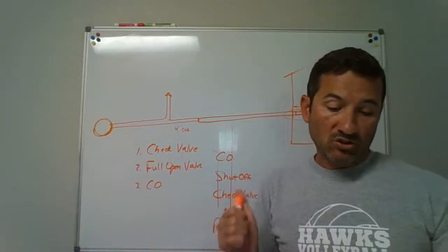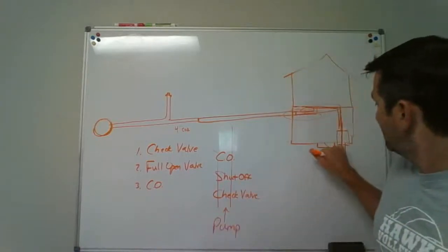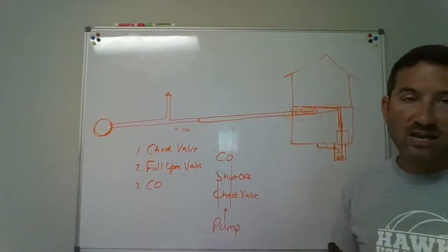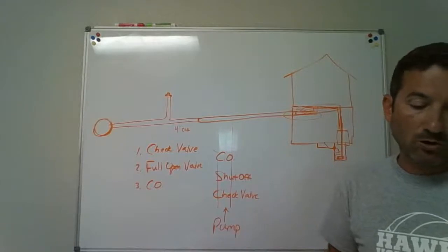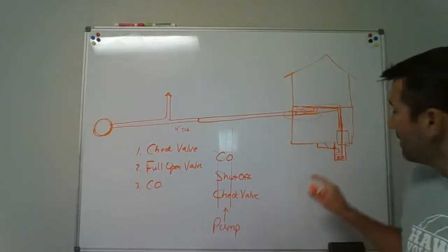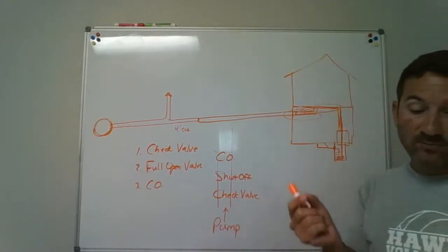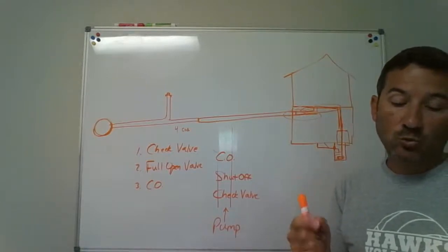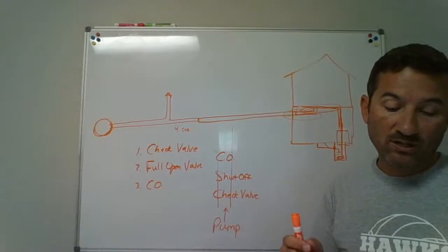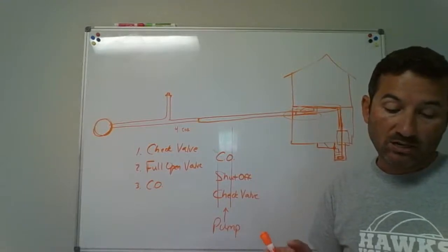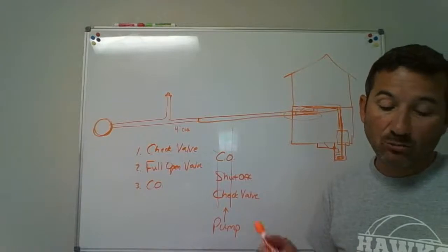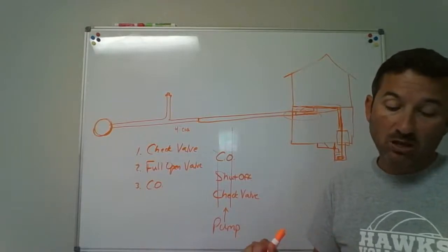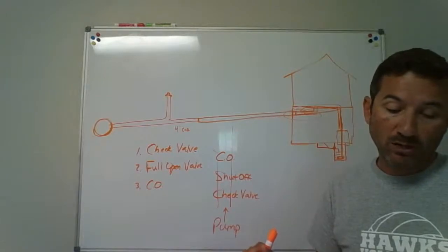Okay. So sump design. The sump and the sump pump. This pump's got to be sized appropriately to be able to pump at the distance that you want and for how much you've got coming through it. The sump pit itself: not less than 18 inches in diameter, not less than 24 inches deep, unless otherwise approved. It's got to be constructed of tile, concrete, steel, plastic, or other approved material. Pit bottom needs to be solid, with permanent support for the pump.